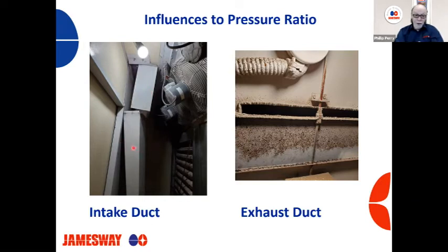And I don't know how long it had been like this. This duct had been knocked off. And so this is going to affect the pressure values and influence your pressure ratio when you check your machine.